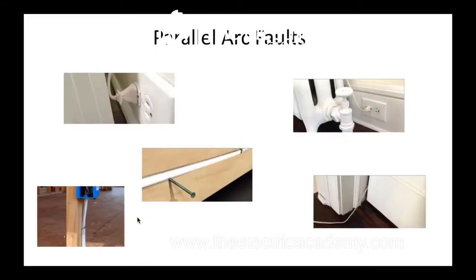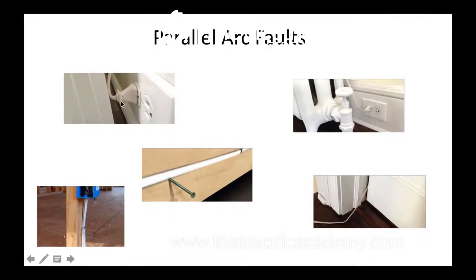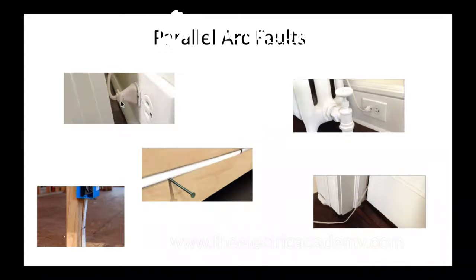More serious are the parallel arc faults. You can get that by having your plug behind a nightstand, pushing into it and causing a short. A parallel arc fault is going to be between line and neutral or line and ground, but not enough to trip the overcurrent device — not enough to trip your regular breaker. But if there's an opening between the hot and the ground or the hot and the neutral, it can arc across and get pretty hot and pretty dangerous, because the only thing limiting that is the resistance of the wire at that point, not the load.